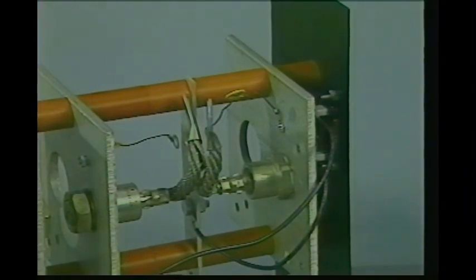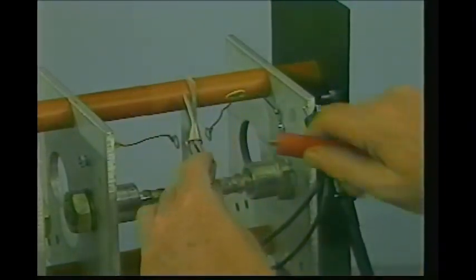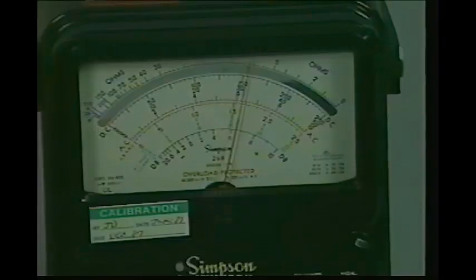You can start with any diode. Fasten one meter lead to the stud. You can use the heat sink. The other meter lead is connected to the pigtail. Observe the meter reading. Notice that it is a low reading but not quite zero.